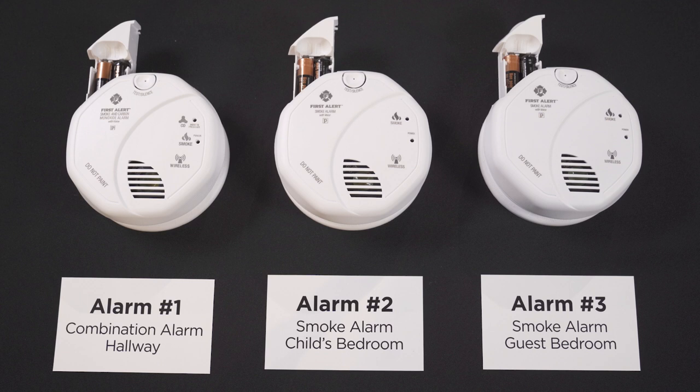To start, we'll activate alarm number one — the battery-only smoke and carbon monoxide combination unit. Insert the batteries into the battery drawer, then close the drawer. You should hear a chirp from the alarm, which means the alarm is activated.